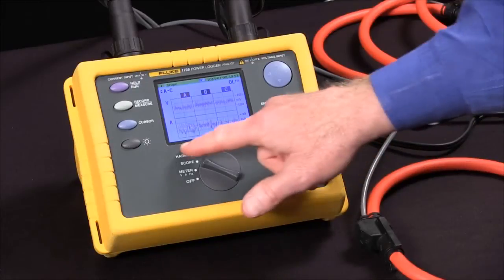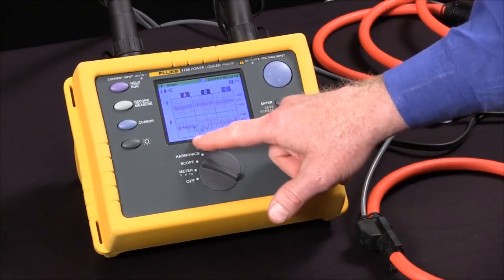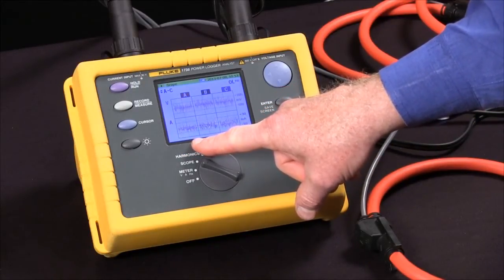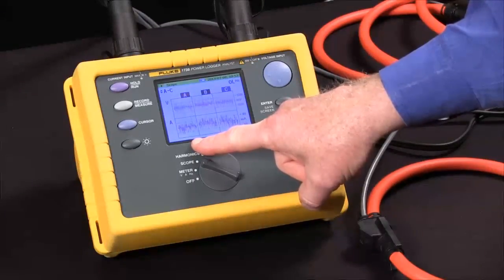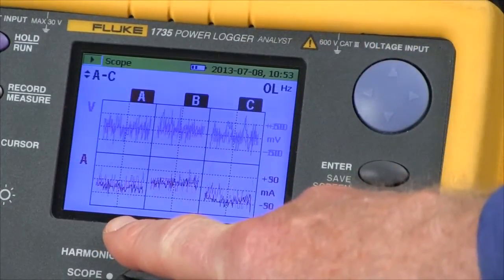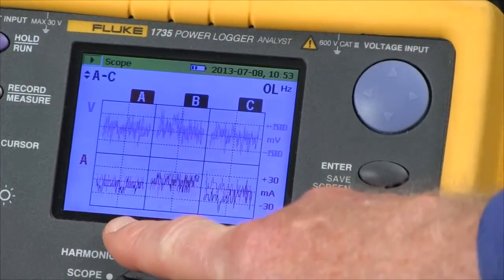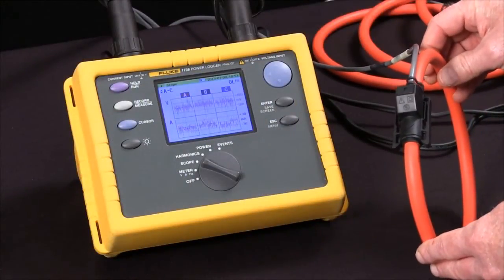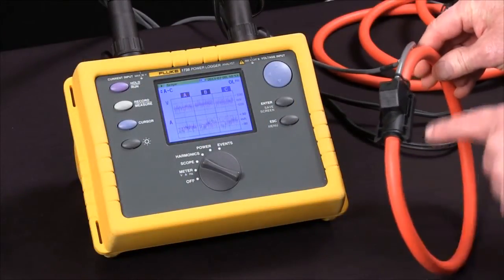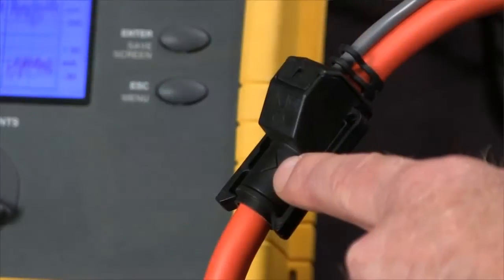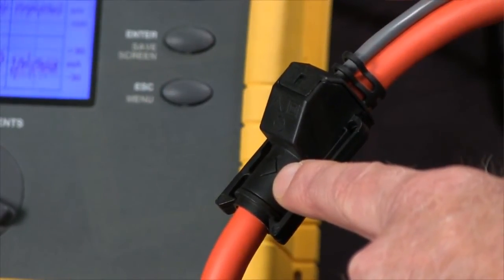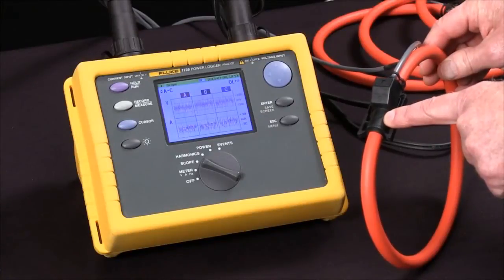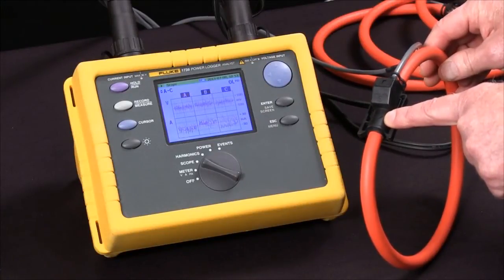At this point we should see voltage and current waveforms for all three phases. We'd expect those to be roughly in phase. If they're not, the issue might be a current clamp that's not pointed in the right direction. All the Fluke CTs have an arrow that should be pointed towards the load — that's how we make sure things are properly aligned.